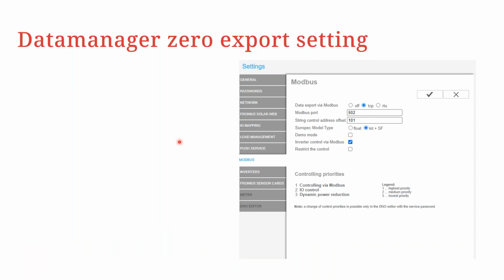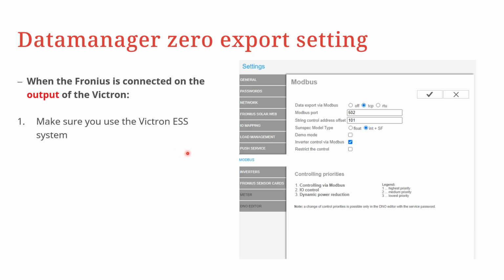So let's now look at export limitation. For an AC coupled system, if you have the Fronius inverter connected to the Victron AC out, then you have to use the ESS system, and then you have to go to the Modbus settings of the data manager. There is a procedure for how you activate the Wi-Fi and the web user interface of the data manager.